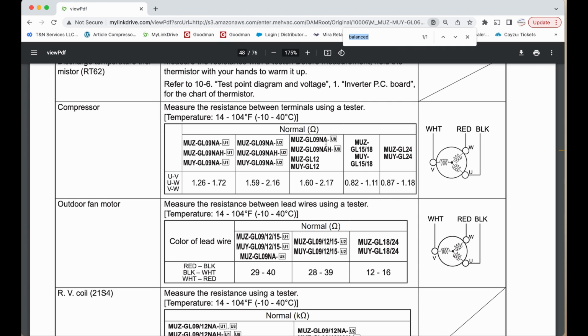And also right here, you have your MUZGL09NA-U8, and they're going to be a little different. They're about the same, but, you know, it is what it is. And then of course the 12 is going to be there. And we're looking right here at the GL15/18, and you get 0.82 to 1.11. So that's how you check the compressor.